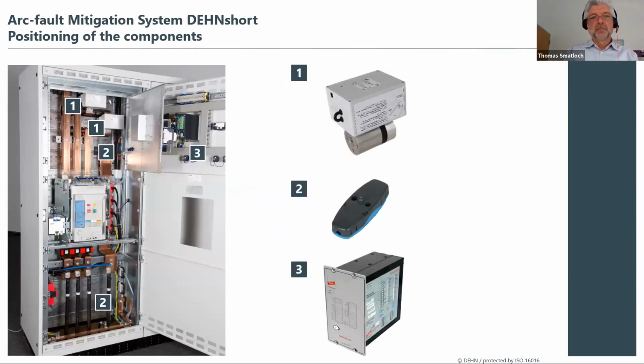Good. So this is about the functioning, and of course here the installation follows the logic of the instruments we have seen here. Number one, this is the short circuiting instrument, and you can find it there in the application on top of this switchgear cabinet. So it has a solid connection to the bus bars, and there is one installed between line 1 and line 2, and a second one between line 2 and line 3, indicated with this one.